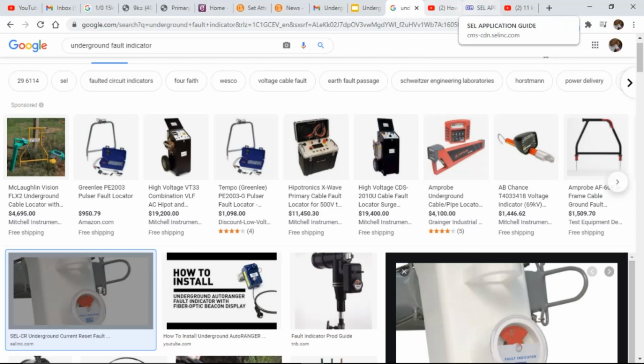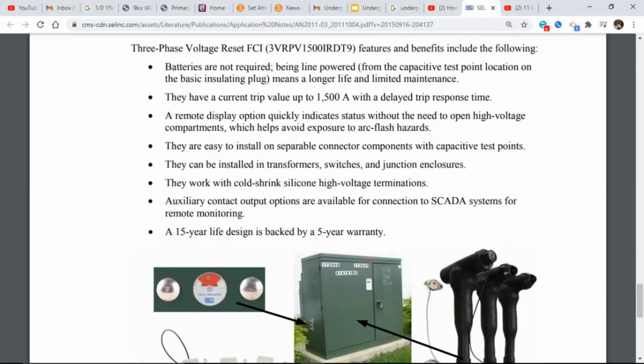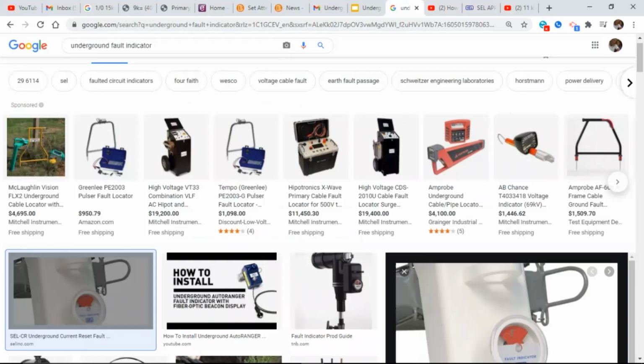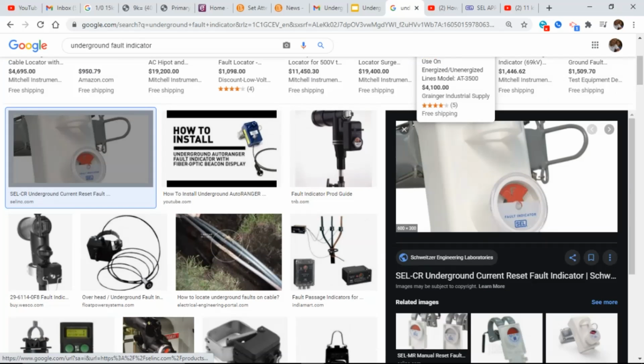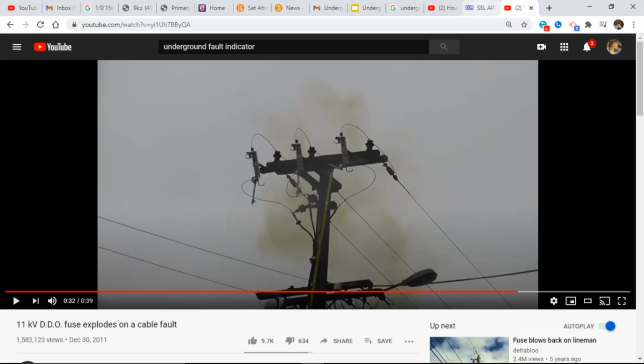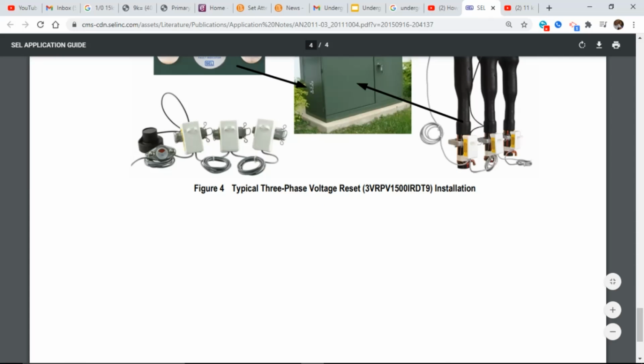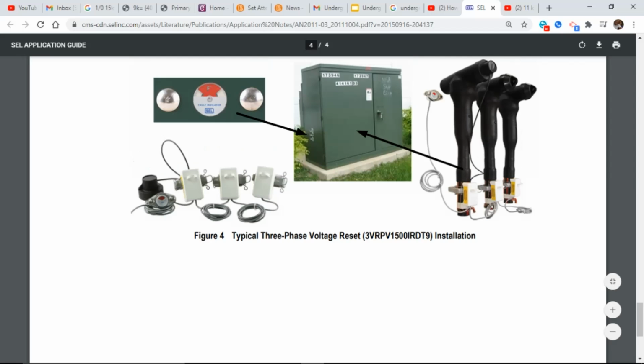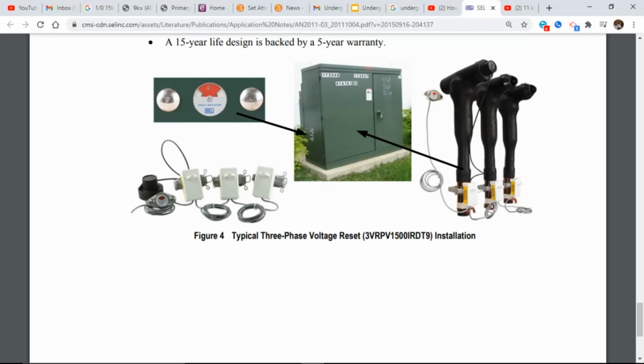First, let's go back to what's going on here. How is this able to determine that I saw a fault? Let me get back to this. Okay, you'll notice right here, you see how the fault indicator is strapped around and coupled to the primary conductor right here? Around each primary conductor. Now, a lot of people assume it's reading amperage around the conductor, and once that amperage gets too high from a fault, it trips the flag.